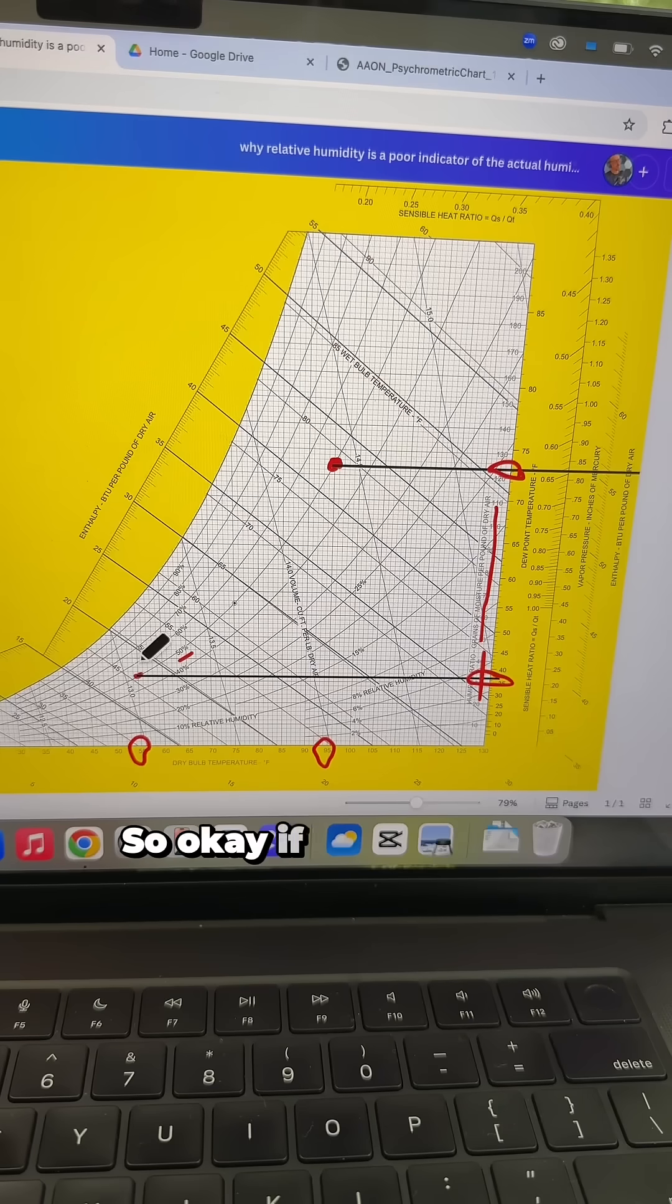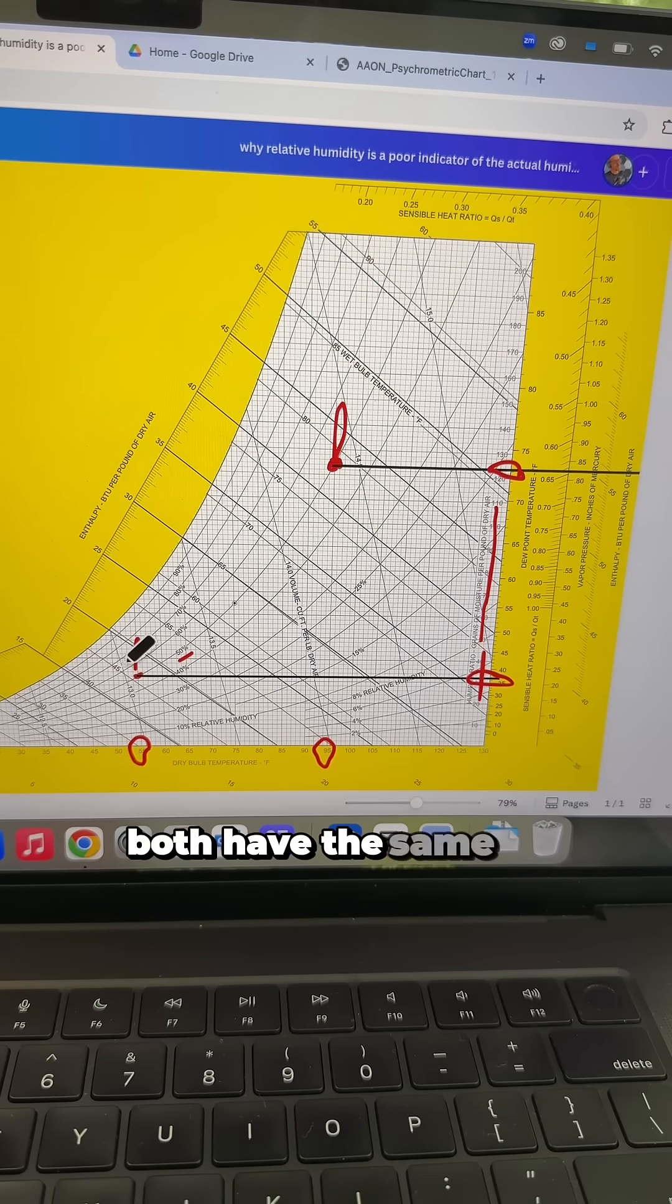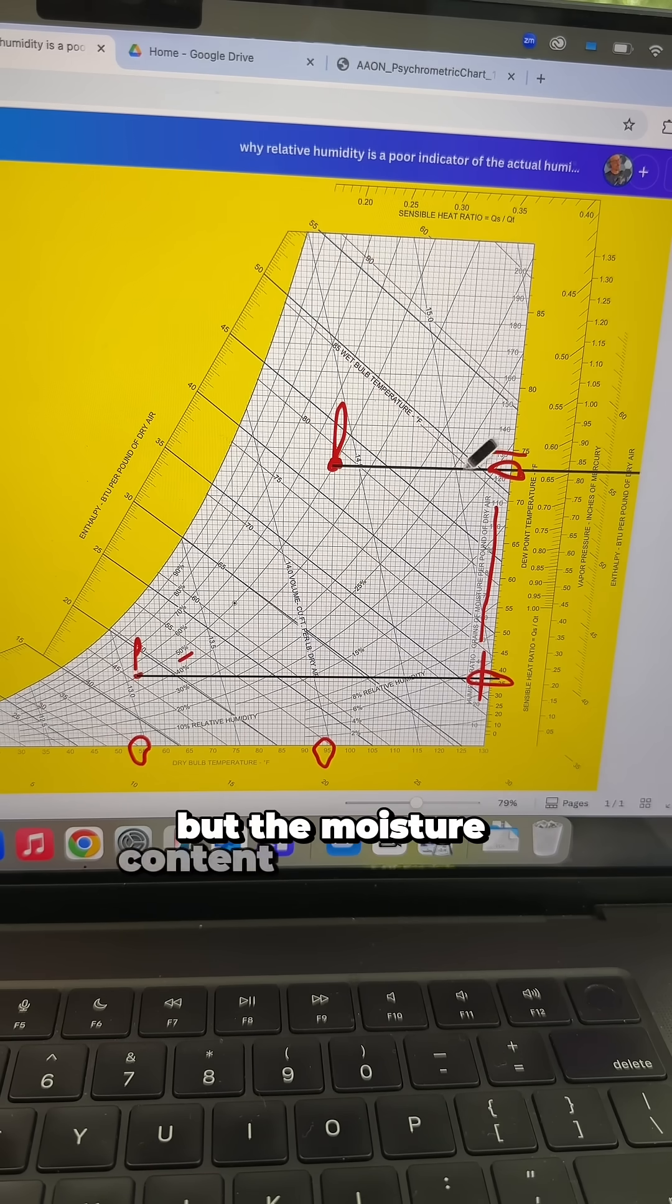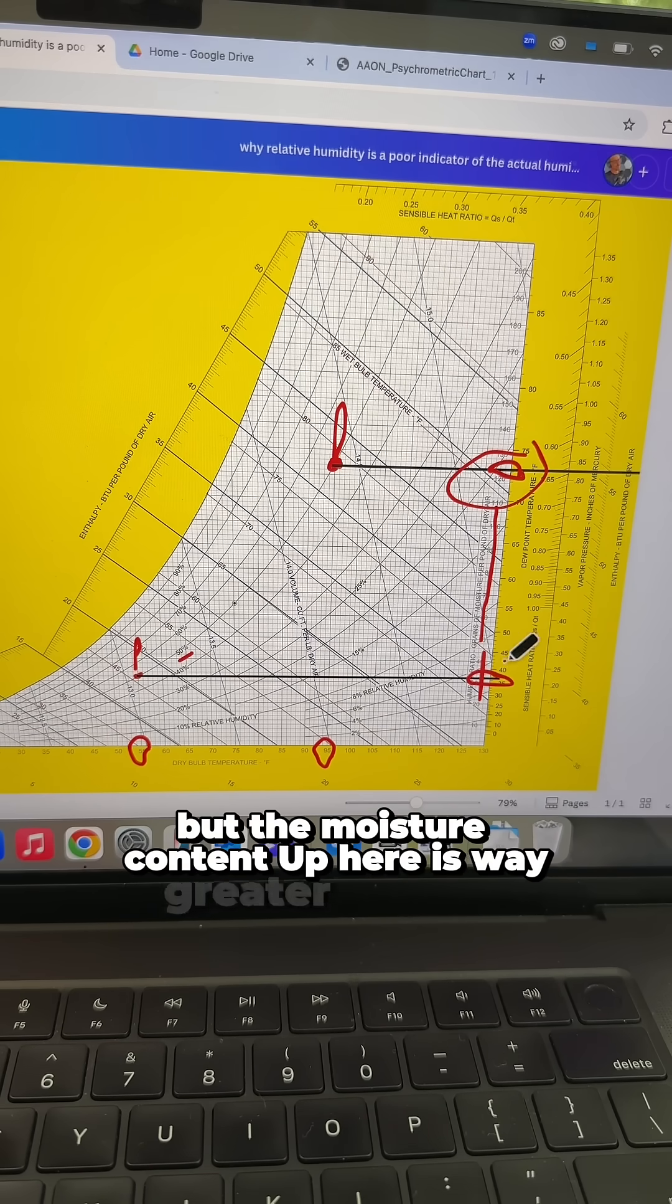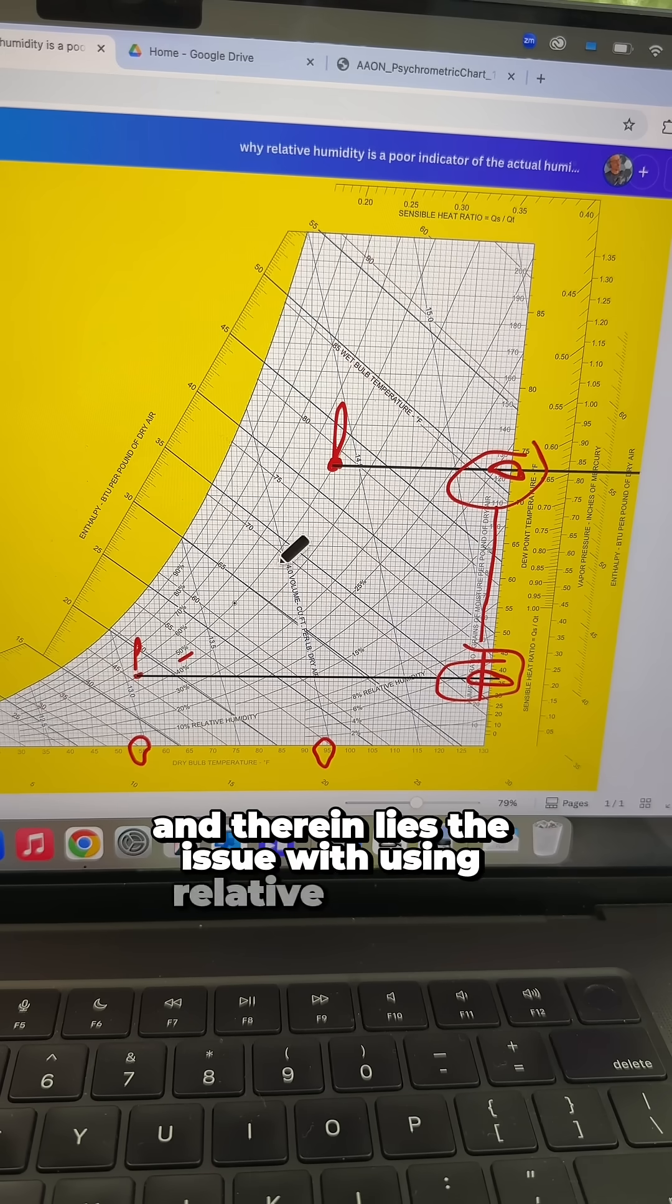So, okay, if we zoom out here, you'll see that this point and this point both have the same 50% relative humidity, but the moisture content up here is way greater than here, and therein lies the issue with using relative humidity.